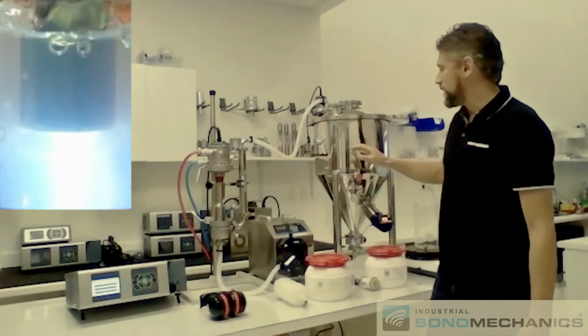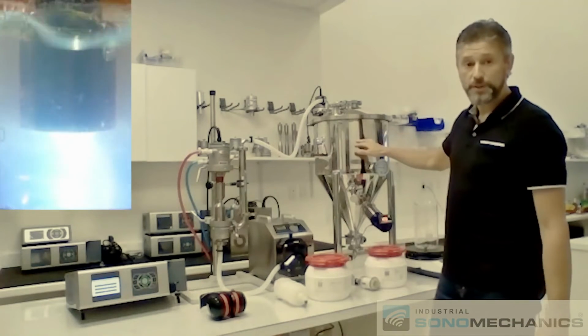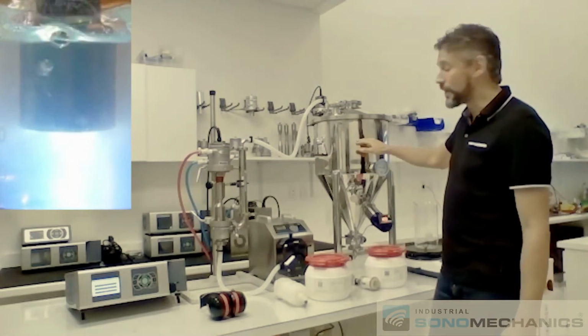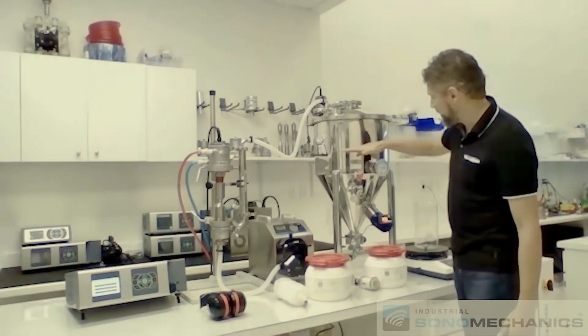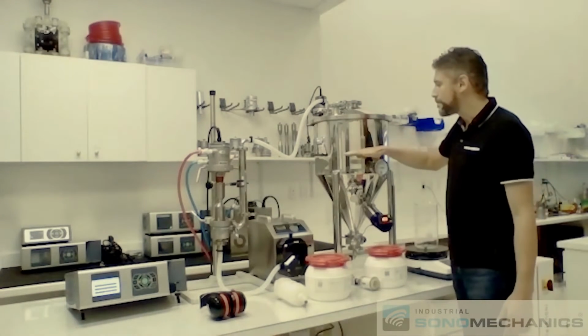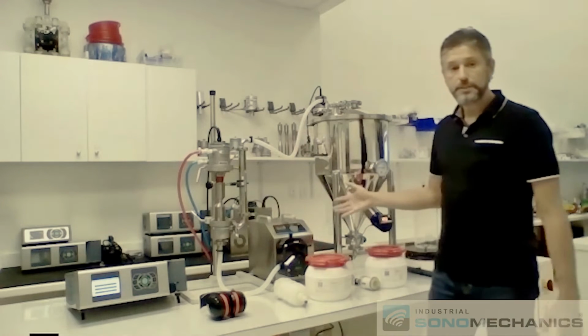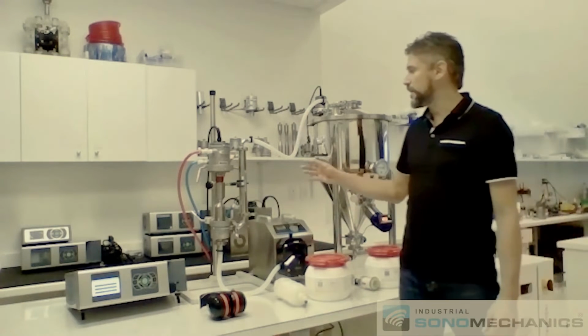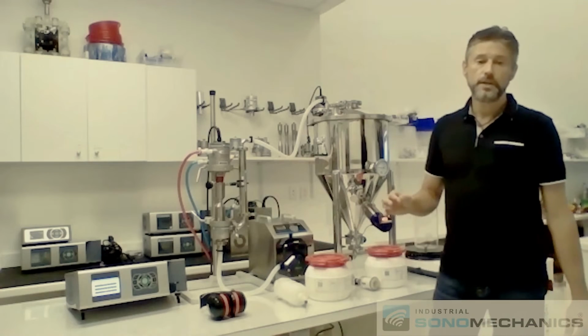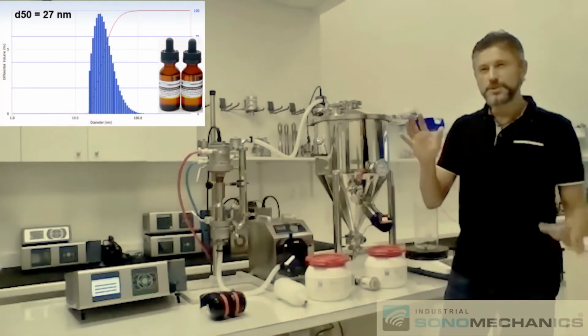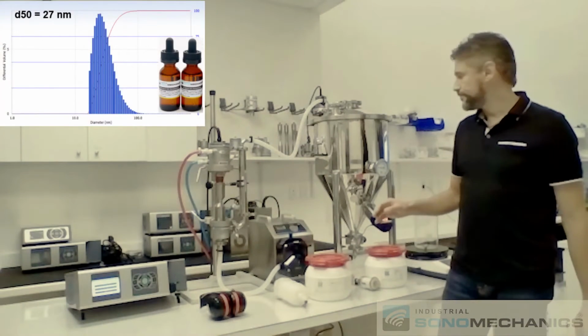And you should expect to be able to process approximately 20 liters of nanoemulsion in 1 hour with the system, which is about half the tank. This is a 50-liter tank. And at the end of this process, when everything is done, you can expect a nanoemulsion with a median droplet size of approximately 25 to 30 nanometers.